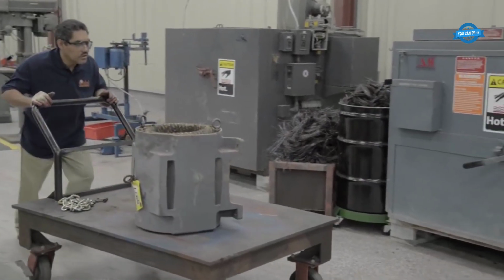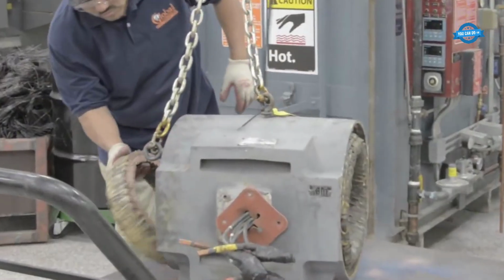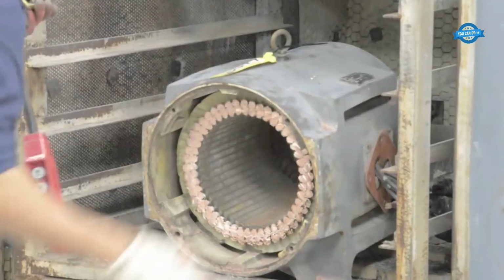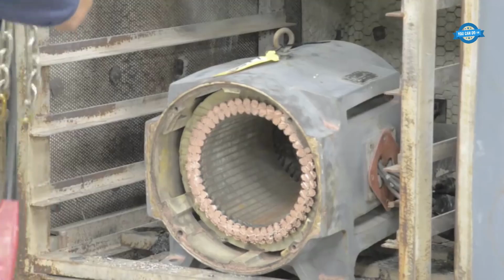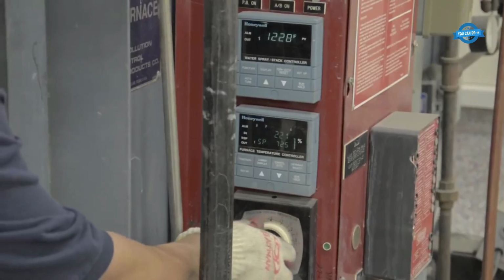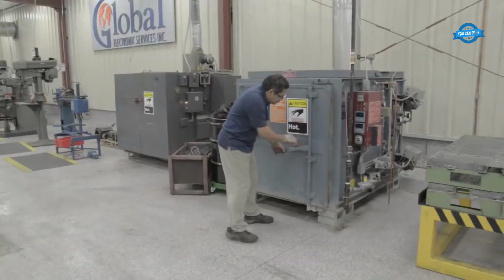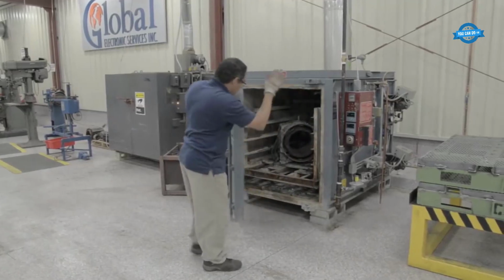Then it is burned in the burn-off oven at high temperature. Varnish and insulation are burned off, making it easier to remove the old windings without damaging the lamination slots.